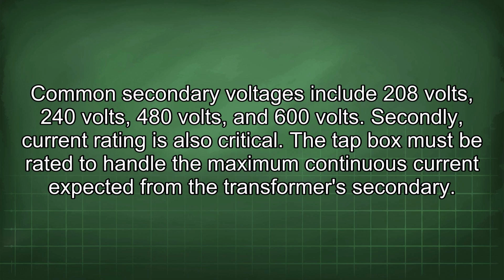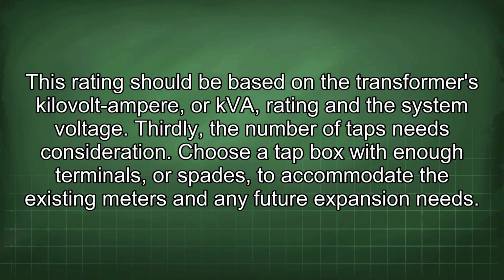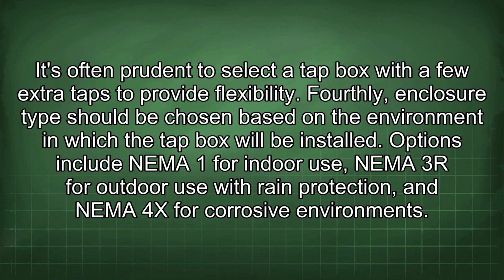Secondly, current rating is also critical. The tap box must be rated to handle the maximum continuous current expected from the transformer's secondary. This rating should be based on the transformer's kilovolt ampere or kVA rating and the system voltage. Thirdly, the number of taps needs consideration. Choose a tap box with enough terminals, or spades, to accommodate the existing meters and any future expansion needs. It's often prudent to select a tap box with a few extra taps to provide flexibility.